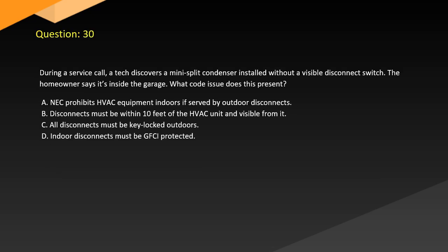Question 30. During a service call, a tech discovers a mini split condenser installed without a visible disconnect switch. The homeowner says it's inside the garage. What code issue does this present? A. NEC prohibits HVAC equipment indoors if served by outdoor disconnects. B. Disconnects must be within 10 feet of the HVAC unit and visible from it. C. All disconnects must be key locked outdoors. D. Indoor disconnects must be GFCI protected.